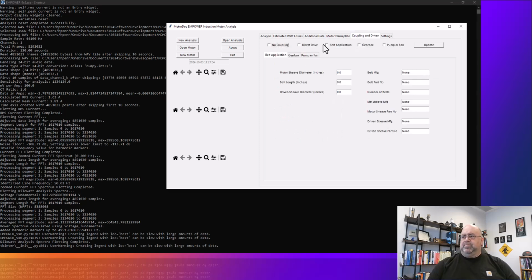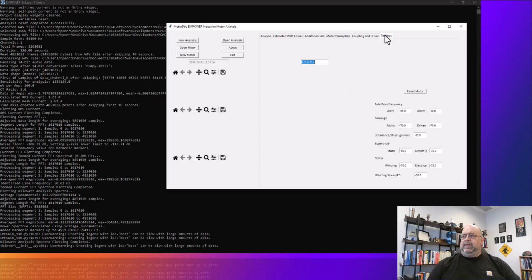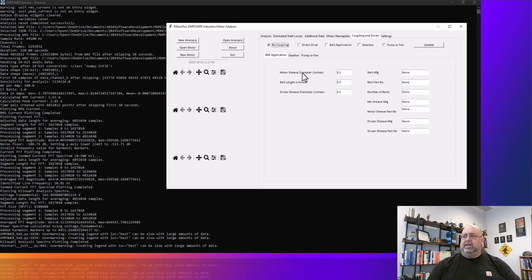It's a small motor. Let's do no coupling, so it's not going to try to calculate out everything else, because with the driven equipment, if I say belt application with a pump or fan, it's going to adjust the speed, including slip, so I can look at the bearings from wherever I take current.